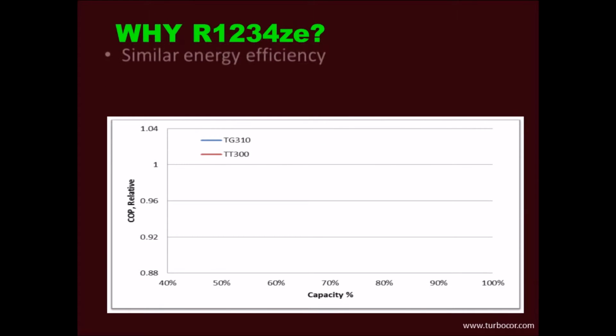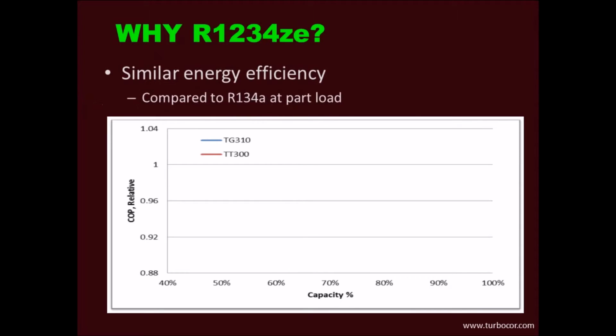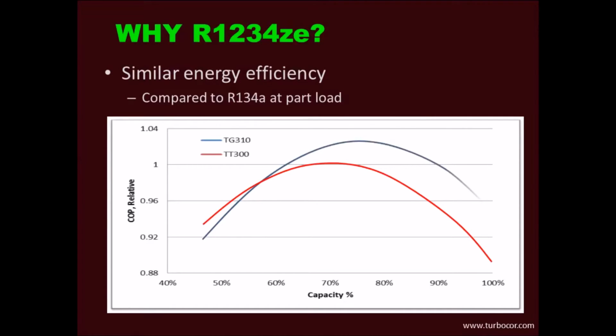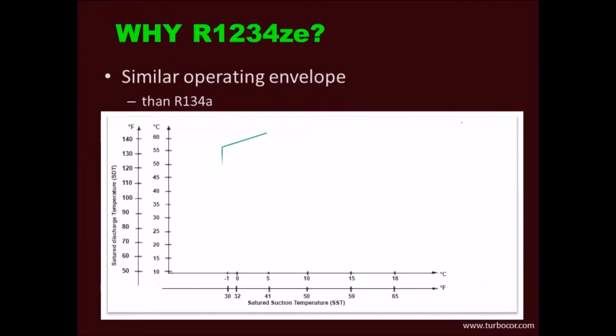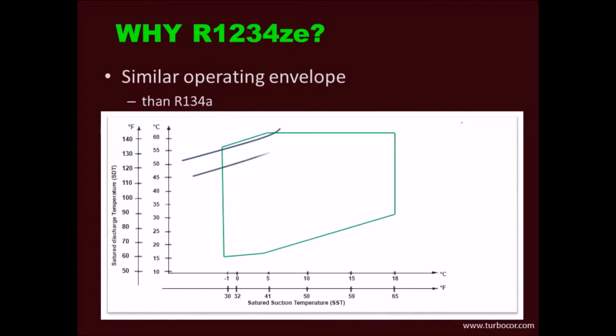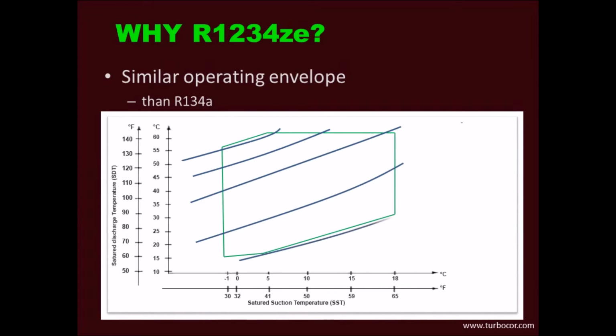Compressor efficiency performance is similar to a compressor using R134A as refrigerant, and the coefficient of performance is almost the same, within plus or minus 1%. Another benefit of the compressor using HFO R1234ZE relates to evaporating and condensing temperatures, or operating envelope. These are similar to the R134A, meaning that the compressor perfectly fits air-cooled chillers where condensing temperatures can reach 60 degrees C.